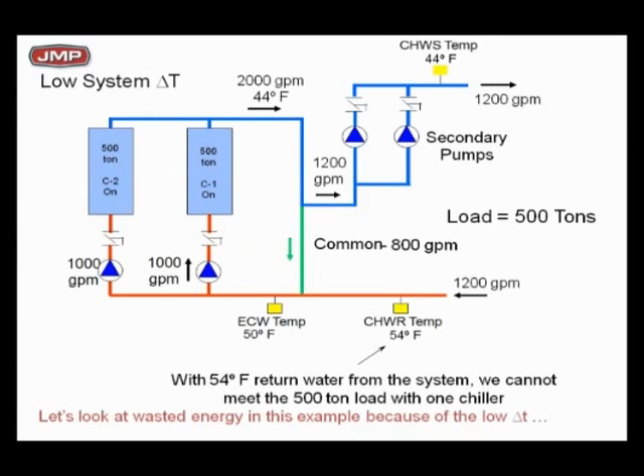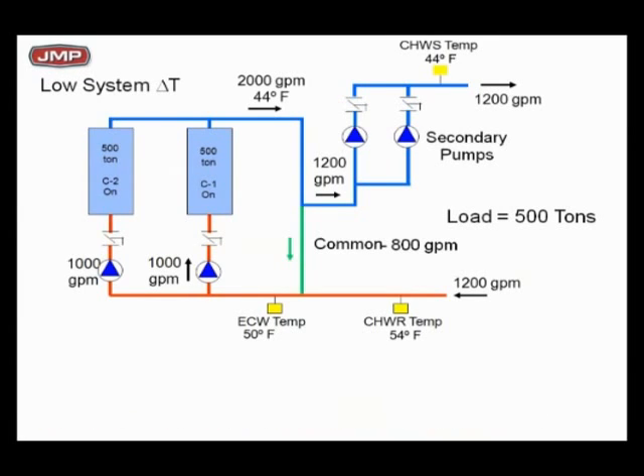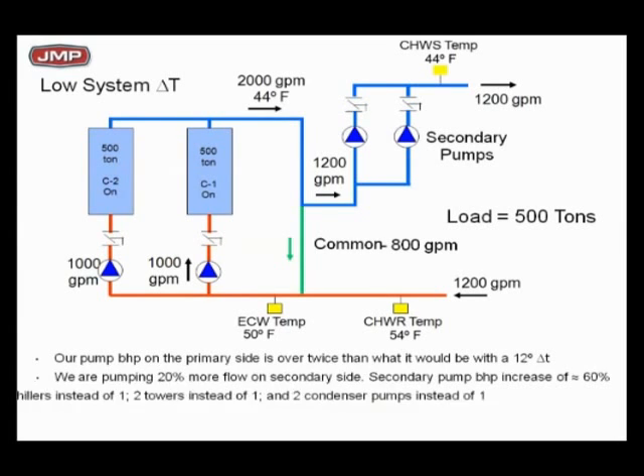You're giving me 54. What does that do to you? Look at all the wasted energy going on in this thing. We got to run two chillers to make 500 tons. So we're double pumping the primary side. On the secondary side, instead of pumping 1,000 GPM, we're pumping 1,200. Friction goes up. I got more pressure drop. I'm having to run two chillers, two sets of pumps, two sets of cooling tower pumps, and two cooling towers. So energy-wise, with low delta T, I'm not getting the 56 back, I'm only getting 54. You're paying a huge penalty in the operating cost, a penalty that has been published, you see it in all the magazines, and everybody says, this is the issue, what are we going to do about it?